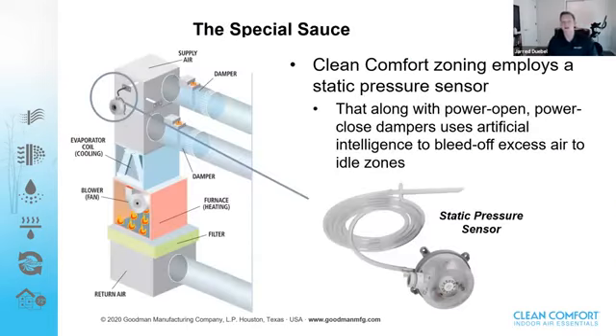So let's talk about how ESP works. In order for it to be a bypass-free system, we have to do something to regulate static pressure. As you see here, the special sauce lies in the static pressure sensor. Again, on a traditional or old school type zone control system, it's pretty common that you might have a section of ductwork that's going to be installed from your supply air right back to your return air.